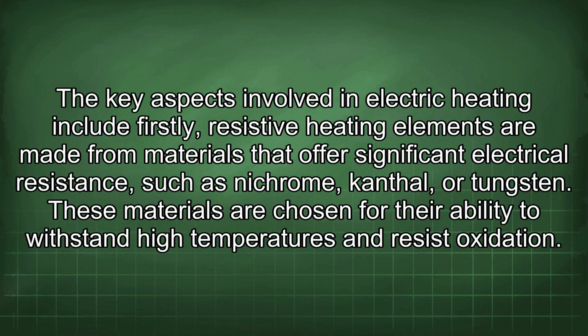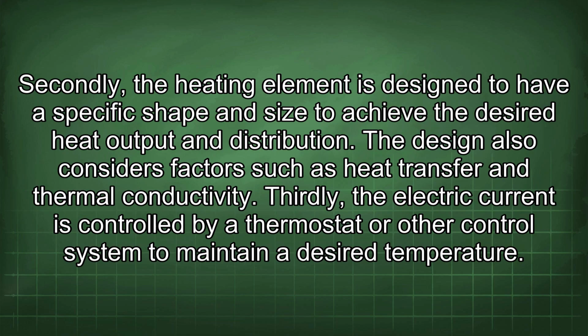The key aspects involved in electric heating include, firstly, resistive heating elements are made from materials that offer significant electrical resistance, such as nichrome, kanthal, or tungsten. These materials are chosen for their ability to withstand high temperatures and resist oxidation. Secondly, the heating element is designed to have a specific shape and size to achieve the desired heat output and distribution. The design also considers factors such as heat transfer and thermal conductivity.